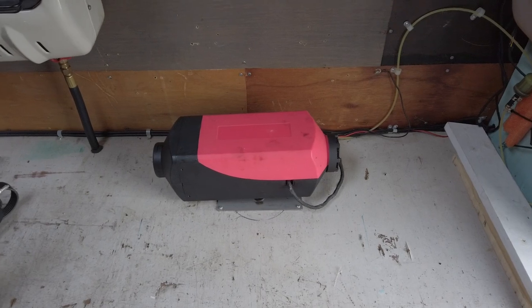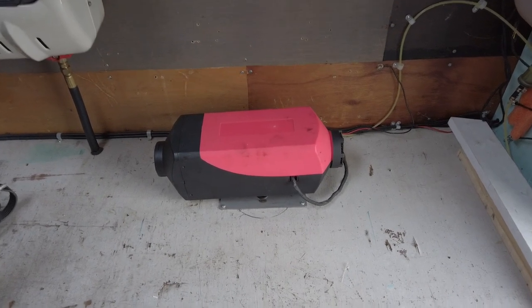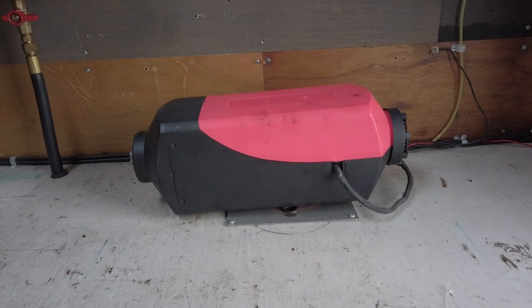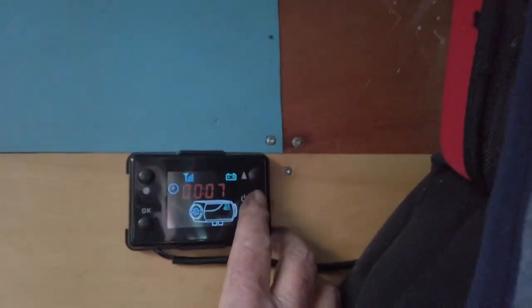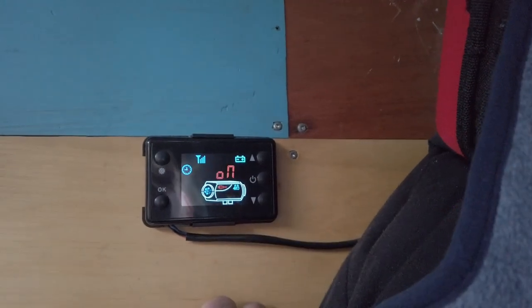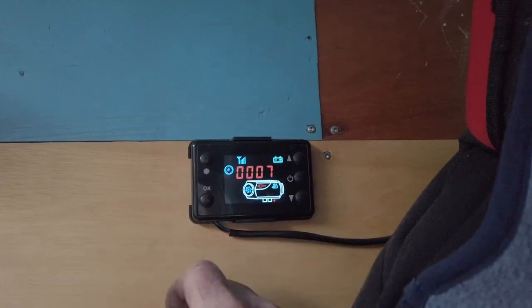So let's put it back together, mount it back on the floor, and then we try it out again. And we still get a fail — error zero seven. The fan stops turning. Flame out. It just can't keep burning.